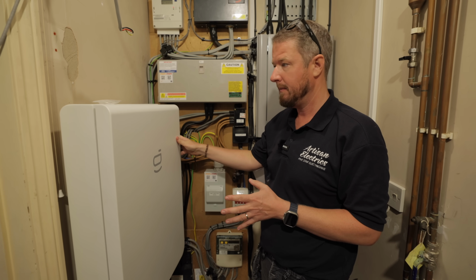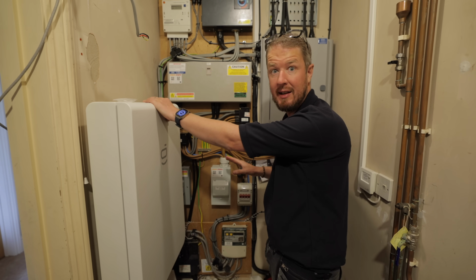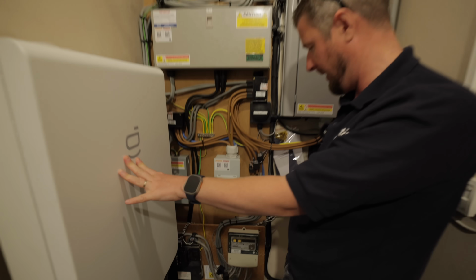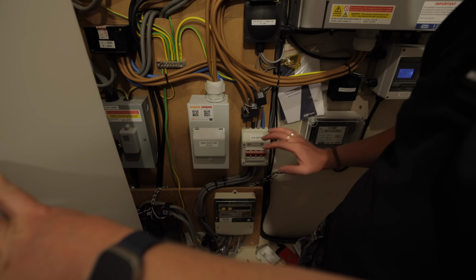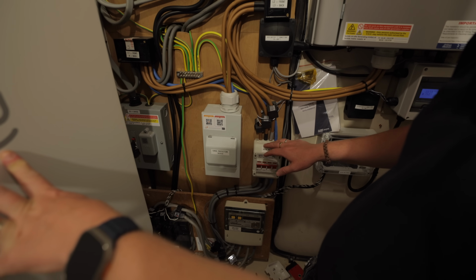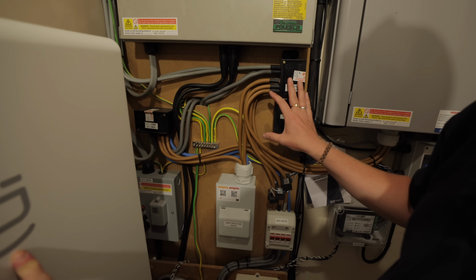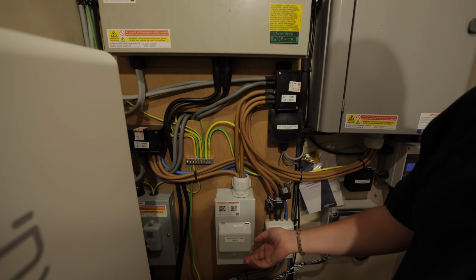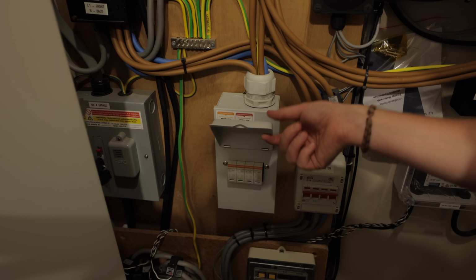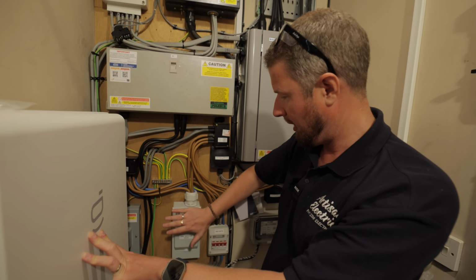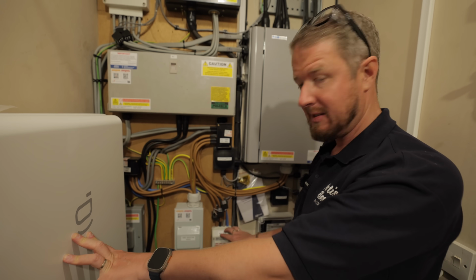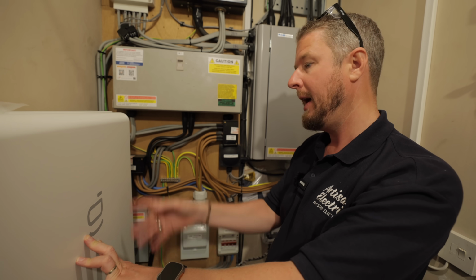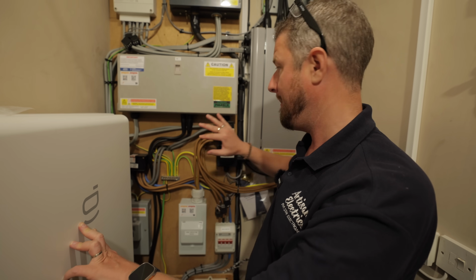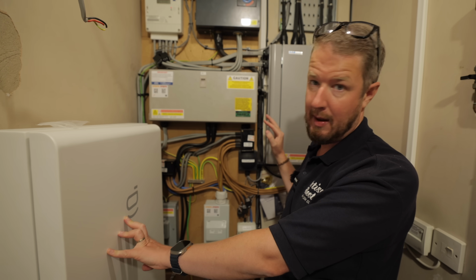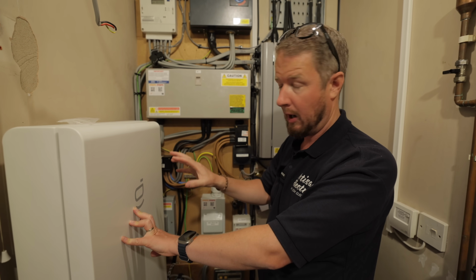This is the gateway, and we're going to reconfigure the whole power setup here. At the moment we've got a main isolator switch for the entire property, which feeds into these Henley blocks to distribute power to the different distribution boards. We've also got a separate surge protection device, but we can remove that because the Sigen gateway has surge protection built in. That will clear up some space, then we'll take these tails out into the Sigen gateway, and out of the backup side back into the Henley blocks, so the entire property will be backed up by the gateway as a full house UPS.